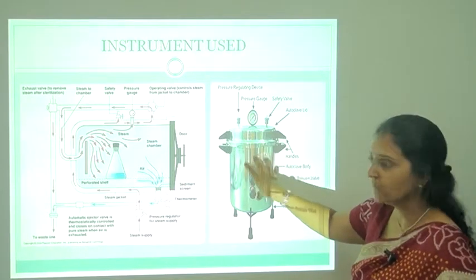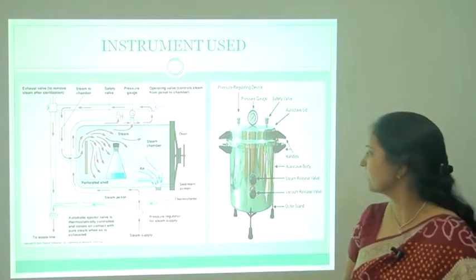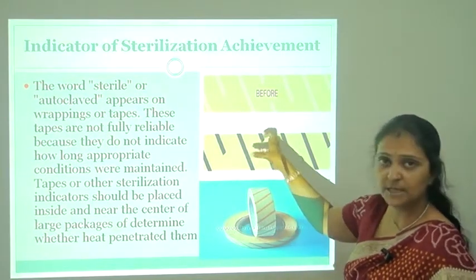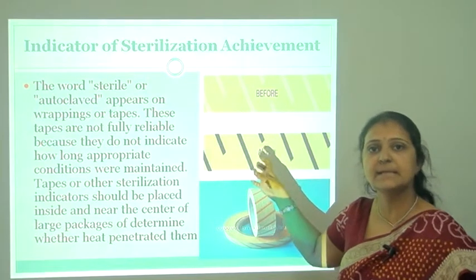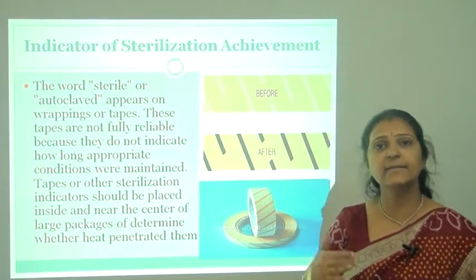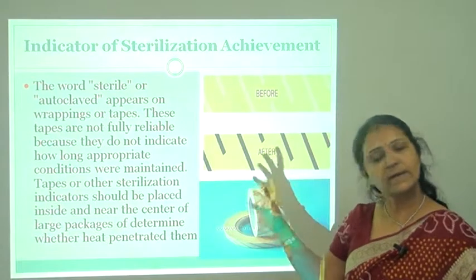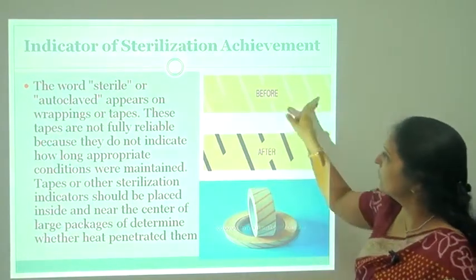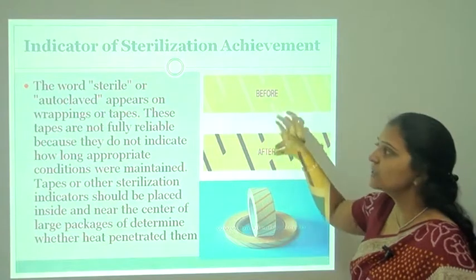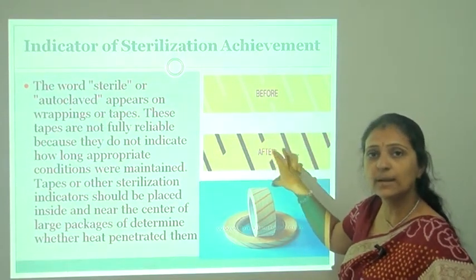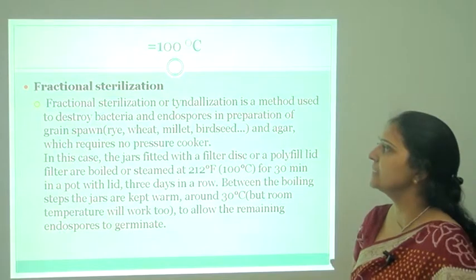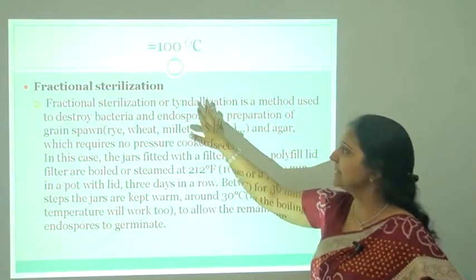This is the structure of the autoclave — this is the vertical autoclave and this is the horizontal autoclave. Now the indicator of sterilization: strips of the most resistant spores, Bacillus stearothermophilus, are used. These spores are the most resistant and require 121°C and 15 LB pressure. You can see the strip before sterilization and the change in color of the strip after sterilization — this indicates whether the autoclave is working properly.